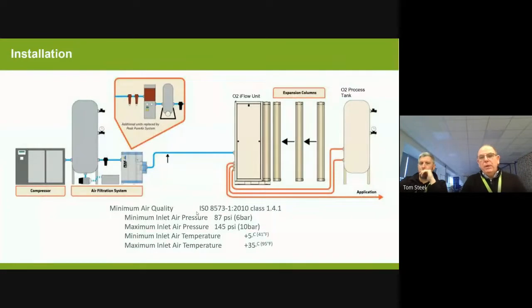So some typical setups, you're going to need a source of compressed air. You're going to need a filtration system. We are talking high volumes of air. For nitrogen, it will be anything between 700 litres per minute up to over 4,000 litres per minute of air is going to be required for the process, depending on your output flow and how many banks of zeolite columns that you have.